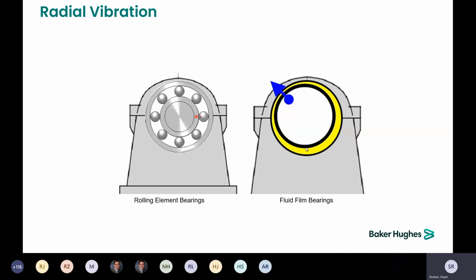However, on a fluid film bearing, the fluid acts as a cushion and absorbs the motion or energy of the shaft motion and does not transfer it as well to the casing. So therefore, using a proximity probe that is mounted to the bearing face or to the bearing cap, looking at the shaft, you do get a view of the motion of the shaft relative to where it's mounted. On very large mass rotors, or where the mass of the rotating component is a higher ratio to the casing mass, you can get pertinent data from mounting a case-mounted sensor on the exterior of the bearing.